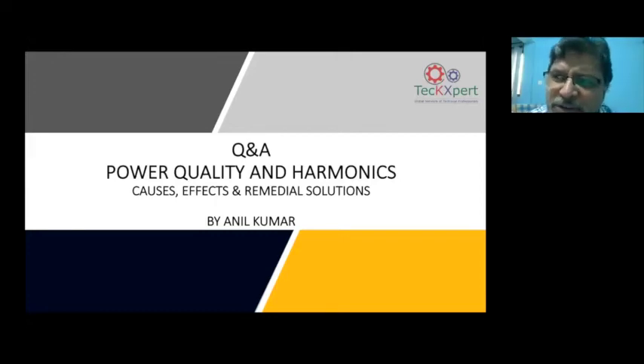Okay. No, I see there are two reasons. One is, as I was telling in the presentation, whenever you have harmonic current in the system, the RMS current also gets affected. That means the reactor rating, for example a 25 kVAR step, is rated accordingly. If you want to rate it for harmonics, it should be rated somewhere about 40 to 42 amps, though your normal current will be 32 amps, when it comes to RMS current. So the reactor current rating can be one aspect, whether the reactor is getting overheated and the problem is happening. Number two, when this particular switching is happening, whether some harmonic resonance is taking place. So either the RMS current is more than what the reactor can handle, or resonance, are the two reasons for this problem.